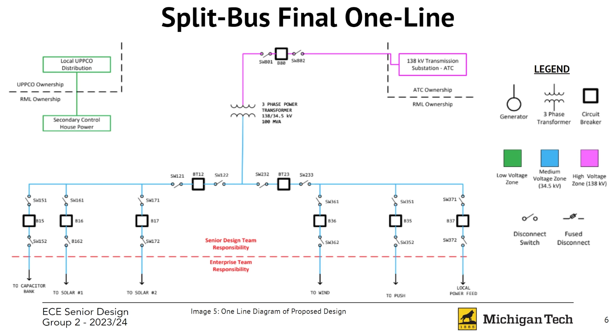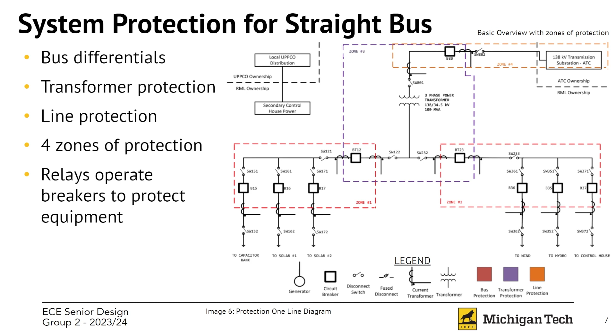Breaking it down further, this is an overview of our protection. At the top is line protection in zone 4, which protects the transmission line leaving the substation. In the middle is transformer protection, which protects the transformer from any possible faults or short circuits. On the bottom left and right, we have two bus differential zones of protection, which help protect the buses from faults that could arise from objects falling on the buswork or animals infiltrating the substation. From that one-line diagram, we then developed the physical layout.